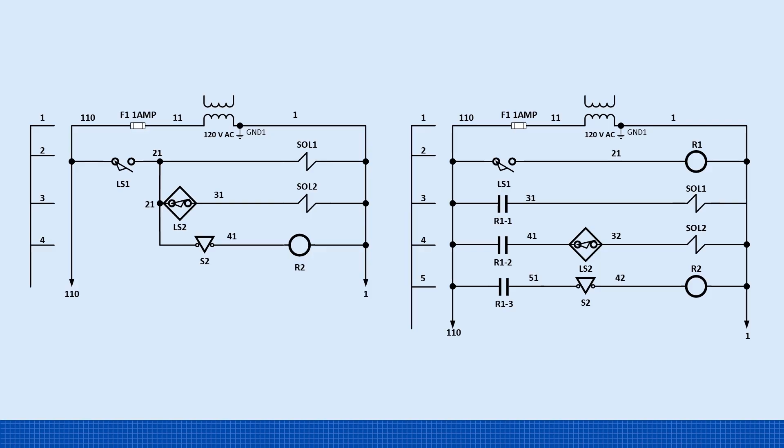Now look at the improved circuit on the right. Here the limit switch LS1 energizes a three PDT relay, R1. Each of R1's three normally open contacts then controls solenoid 1, solenoid 2, and relay 2 separately. This design keeps the schematic clean and well-organized. More importantly, LS1 no longer carries the total current of all three loads, only the coil current of R1.